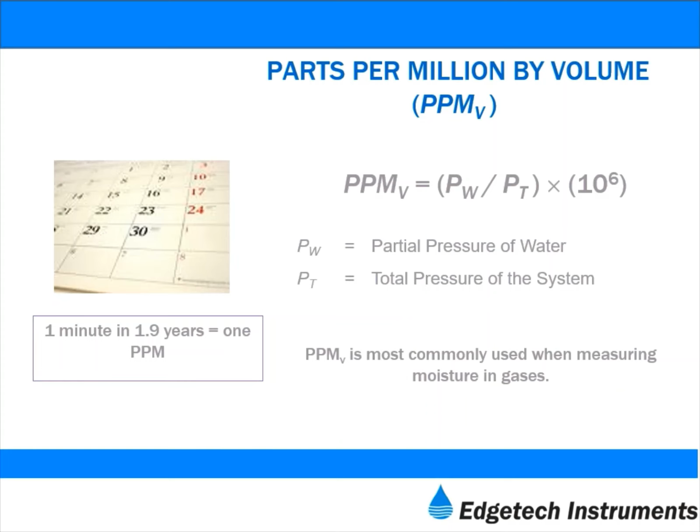So the dew point is measured by the sensor. A total pressure must be measured typically by a pressure transducer. Those two values are brought into a microprocessor. The microprocessor does the math. First, it would have to convert the dew point to vapor pressure, maybe using the Goff-Gratch equation. The total pressure comes in straight away from a pressure transducer or a pressure transmitter. So with those two values, you do the simple math, and that gives you the part per million value.